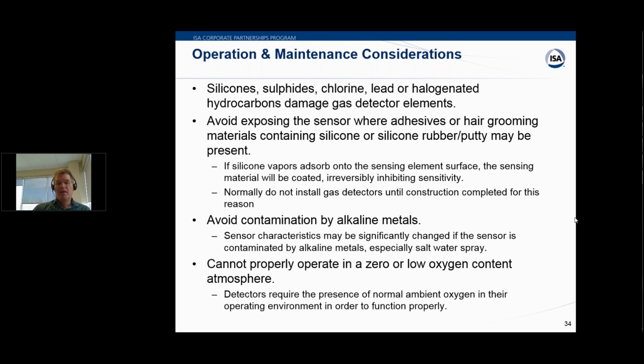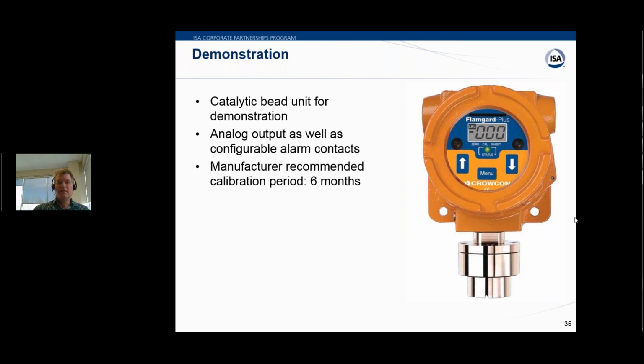It gave a false reading. As we've shown, all of these detectors, because they're based on a chemical reaction of one form or another, pretty much all need oxygen. So if your oxygen is too low, then your detector will not work. A gas detector typically will not work in a nitrogen atmosphere. And we are using, as I said earlier, a catalytic bead unit for this demonstration. The Crowcon unit that we have here, they recommend a calibration every 6 months. And as is the case with a lot of gas detectors, they have an analog output as well as configurable alarm contacts, so that you could directly wire to a local alarm or relay panel.